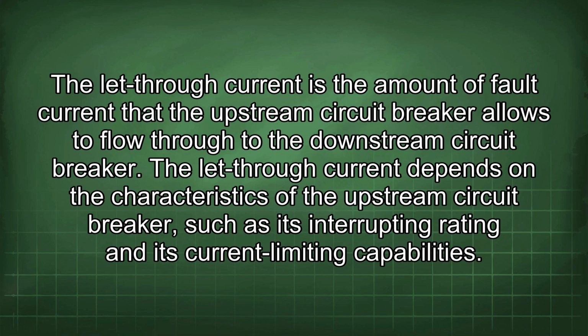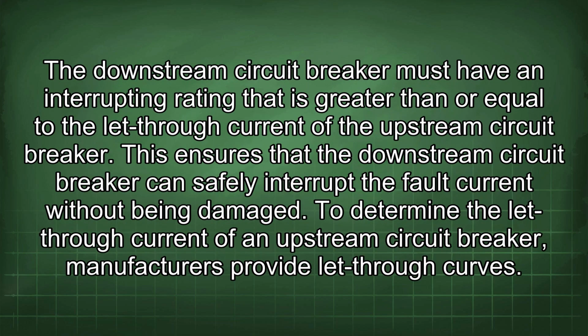downstream circuit breaker. The let-through current depends on the characteristics of the upstream circuit breaker, such as its interrupting rating and its current limiting capabilities. The downstream circuit breaker must have an interrupting rating that is greater than or equal to the let-through current of the upstream circuit breaker. This ensures that the downstream circuit breaker can safely interrupt the fault current without being damaged.